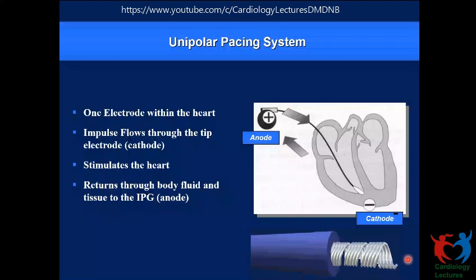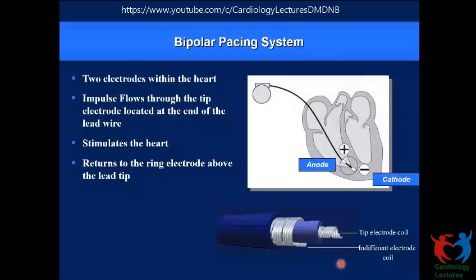And as I said, what you use today is all the bipolar system, where the can is not acting as an electrode anymore. Both the anode and cathode are there in the pacing lead itself. So the inner electrode, just like a unipolar one, has an insulation that ends at the tip, which is in this case placed in the right ventricular apex, and the current returns through the proximal electrode, which is the anode, which is the outer electrode of this pacing lead, and that has one more insulation on this.